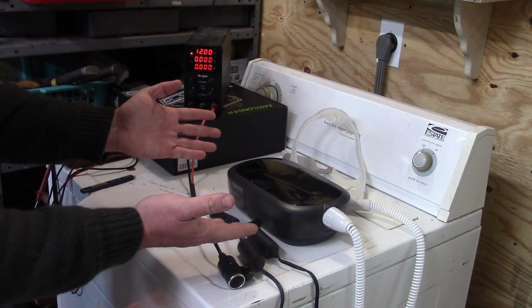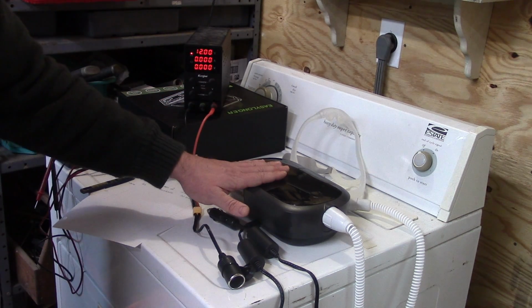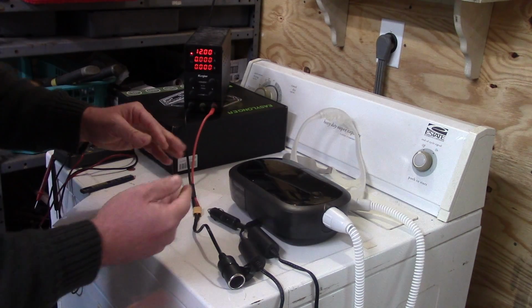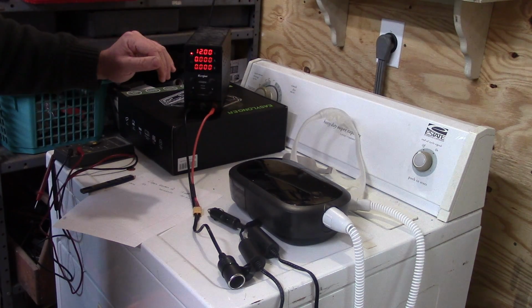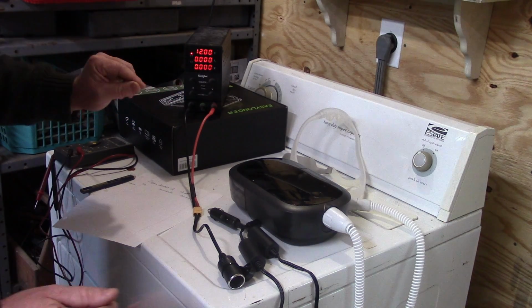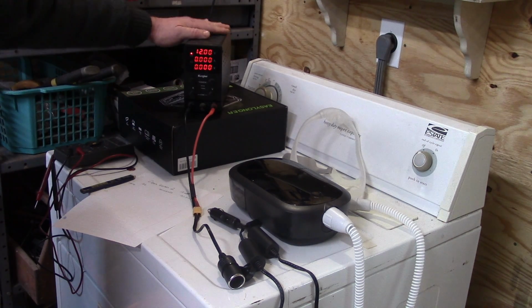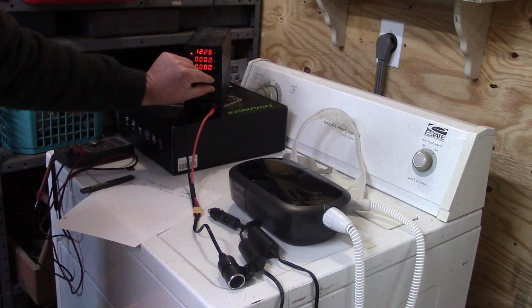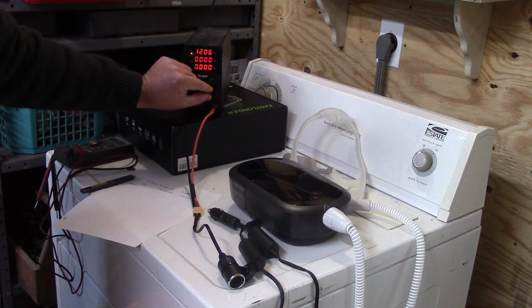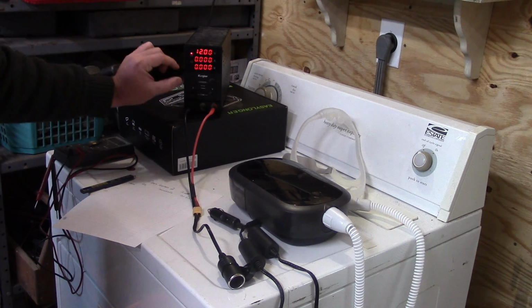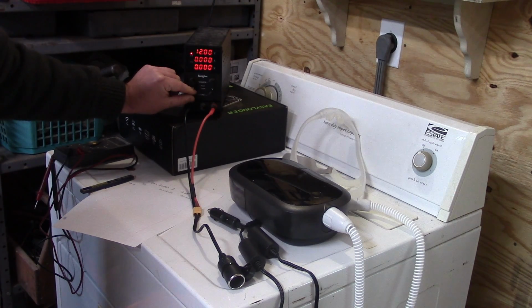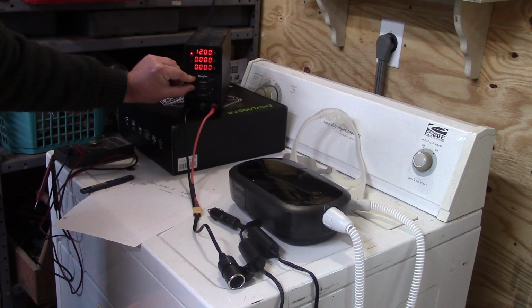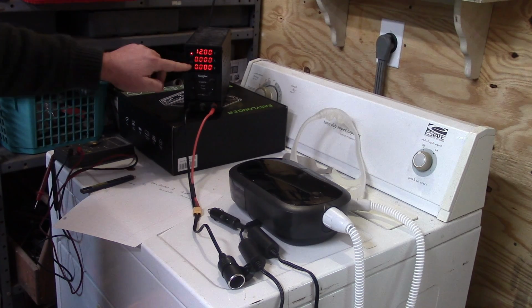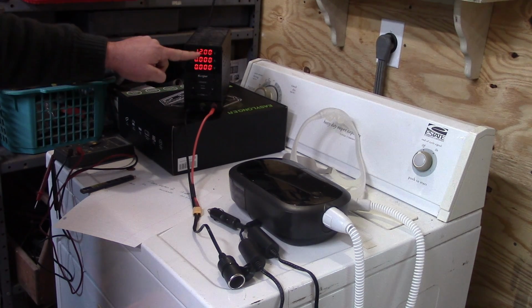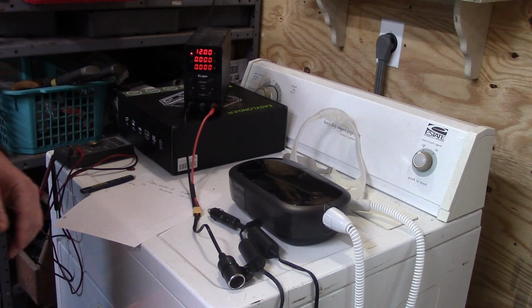So first off, let's determine how much power a CPAP uses. This is the DreamStation 2. I got this recall replacement for the toxic DreamStation 1, which will be the other CPAP that we test. What I have here is a variable power supply. I have it set to 12 volts, so you can adjust the voltage on it. You can also adjust how many amps go through it. I have the amps, the current that it will flow, maxed out all the way, so this will go up to 10 amps. And this bottom reading calculates volts times amps equals watts, and it shows us how much it's using.